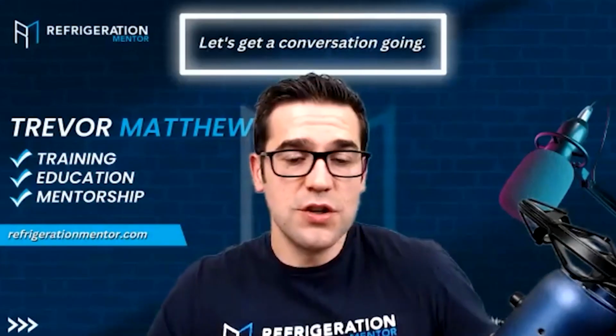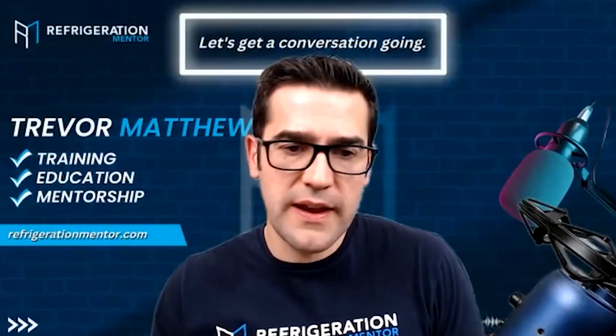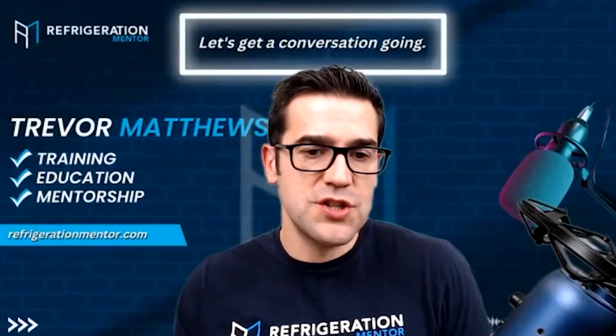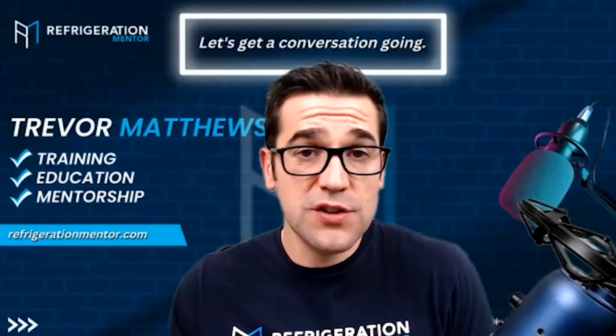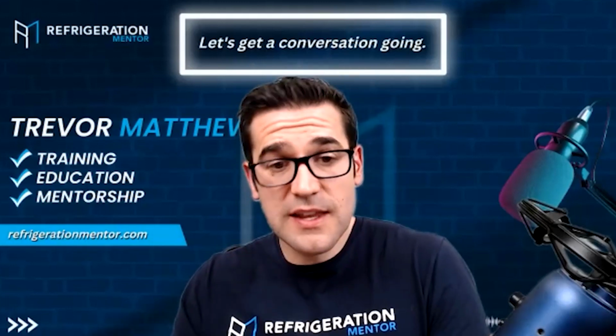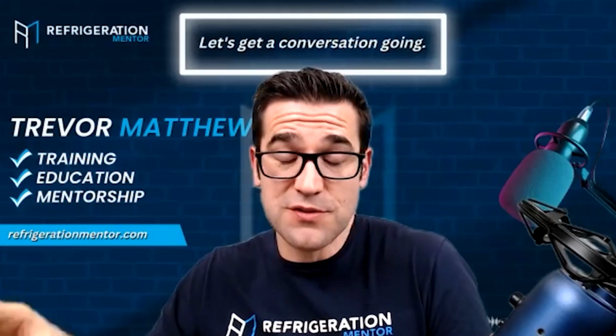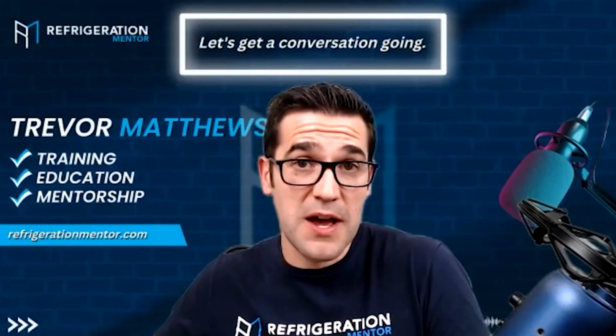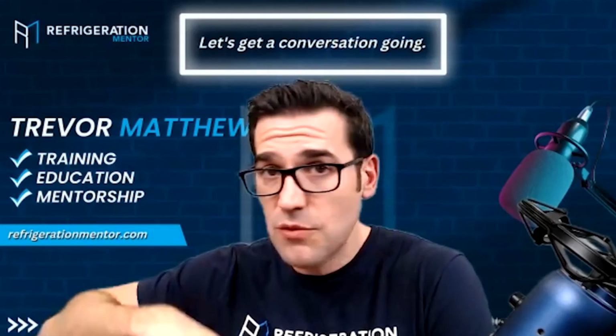Please don't mess with that cycle. Very good. You shouldn't in any of these controllers. That's 100% because it's going to change how it works and you'll run into issues. And when you run into case issues, then you run into flash tank issues. You run into high pressure valve and flash gas bypass valve issues because all this system works together.